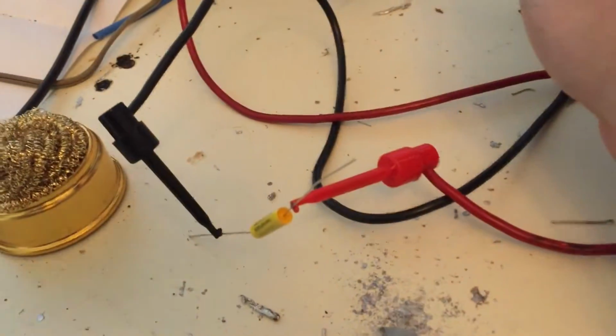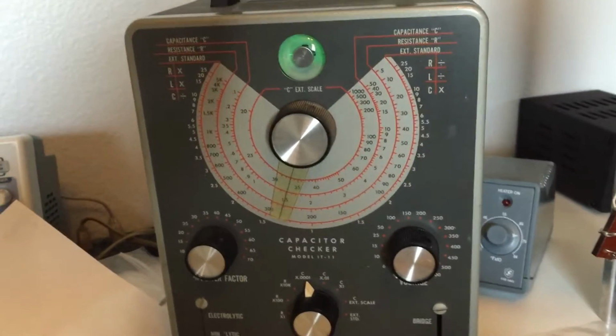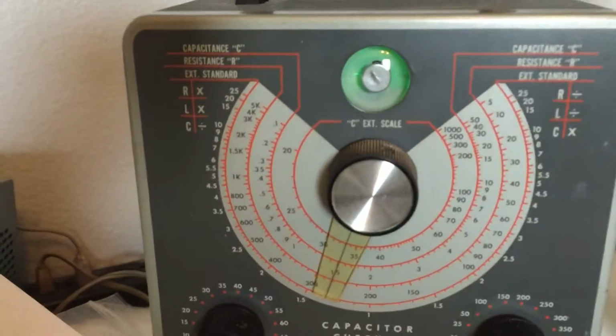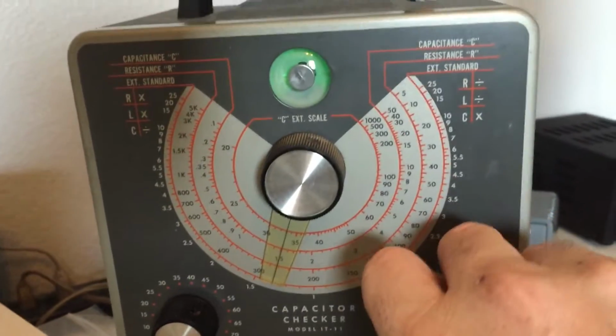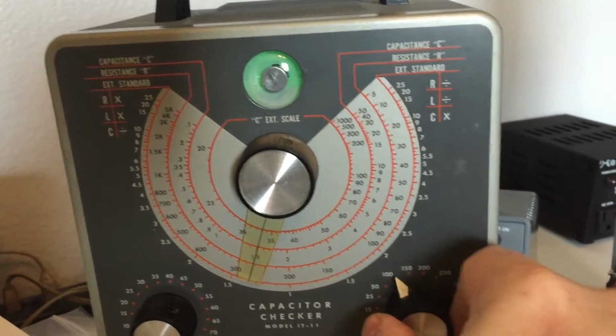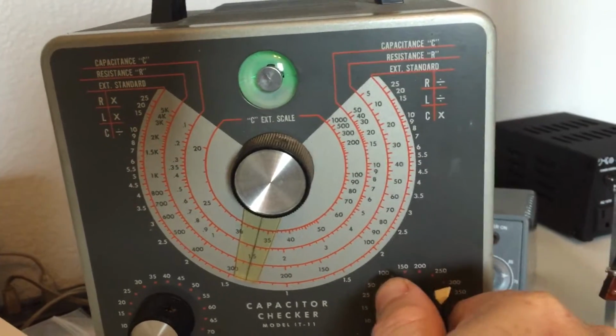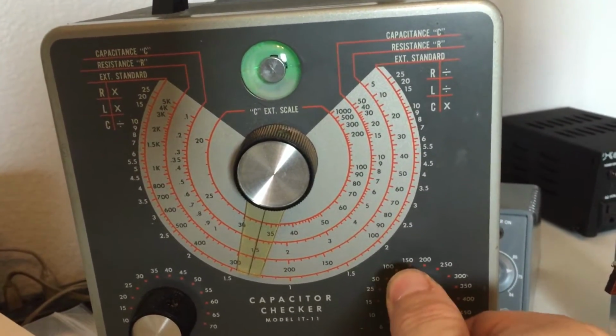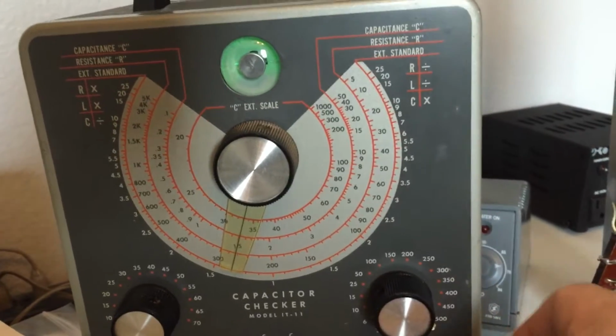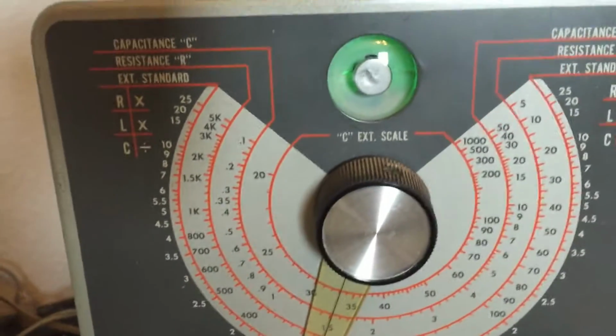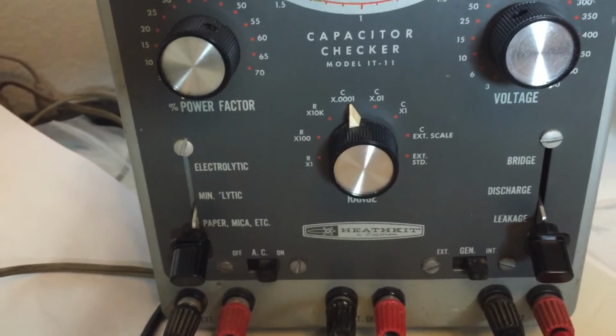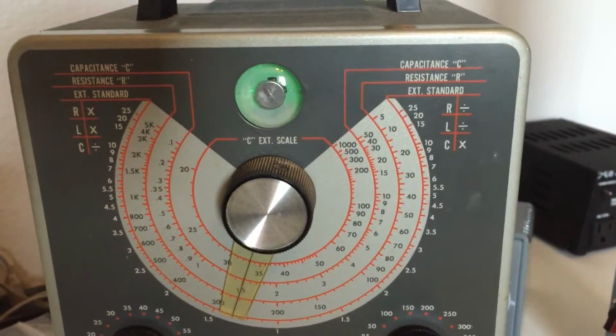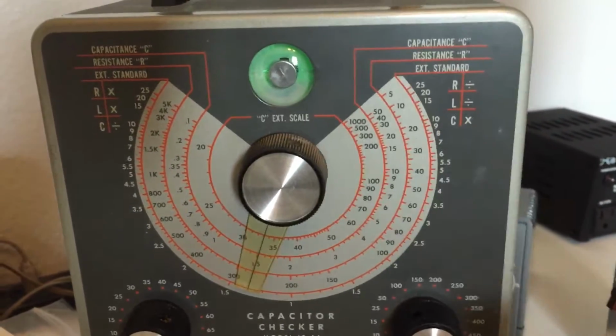By comparison, I'd like to show one of the new capacitors in place here that replaced one of the old ones. I'm going to hook it up to the tester, crank it up all the way to max voltage, and we're going to watch it climb from 3 all the way up to 100, 250, 350, 450, 500, 600 volts — and that's on the lowest setting, which will detect like 3 microamps or less. So that's what we mean by no leakage.